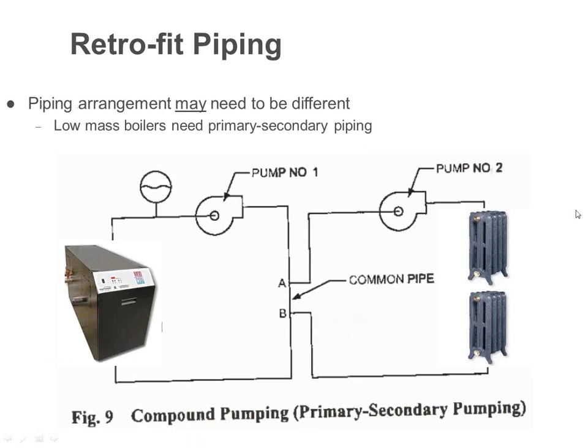Okay, venting is one thing that is critical. Piping is also very critical. This is where we had, back in 2000, a lot of our problems. The piping arrangement may need to be different, but most of the time when you're dealing with a low mass boiler, they definitely need primary, secondary piping. It just keeps you out of trouble. There are some boilers that have it built in, that's great. If you're not sure, build it in. You ain't going to hurt yourself.